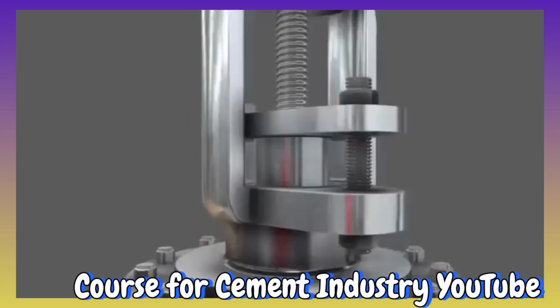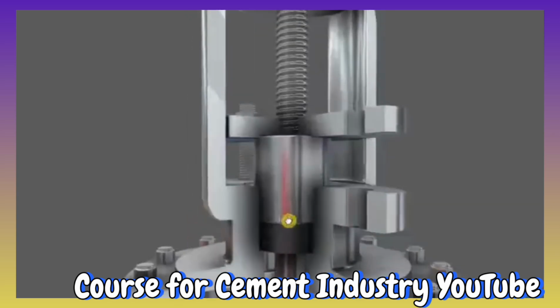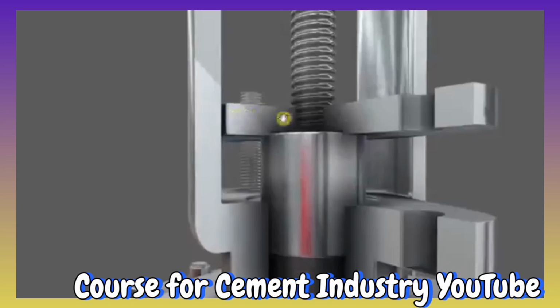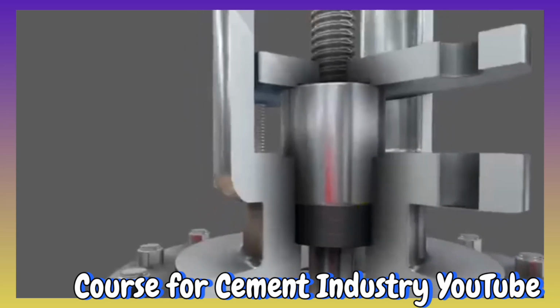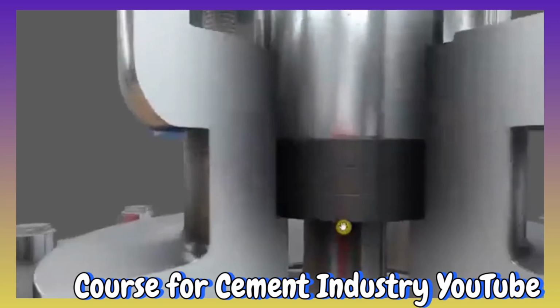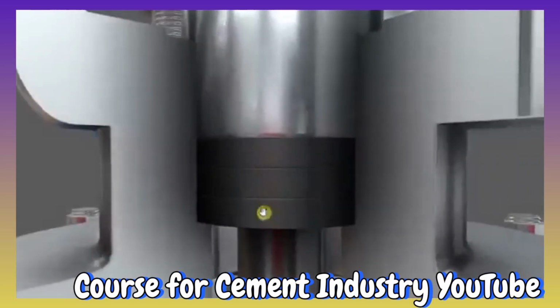So let's have a look at a few of those components now so we can figure out how the whole thing works. So we tighten up this plate, the follower plate. It's going to push down on the gland, and as we do that we're actually going to put pressure onto this black area here, this packing.